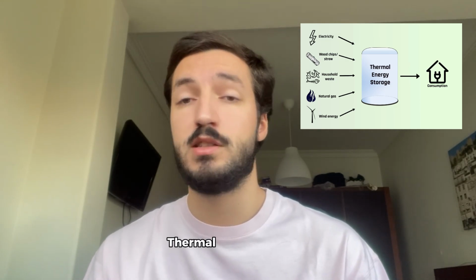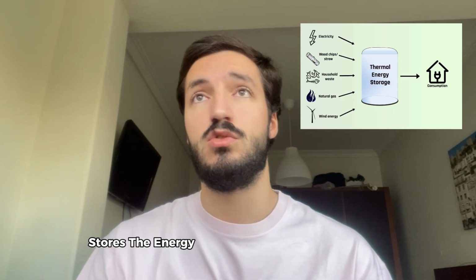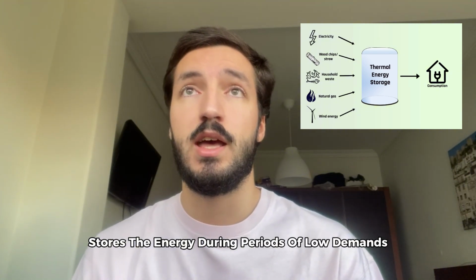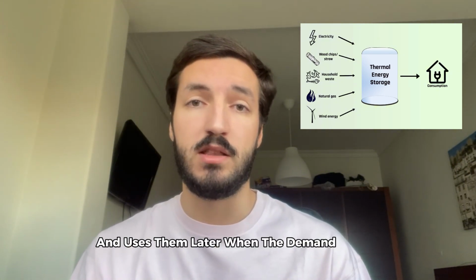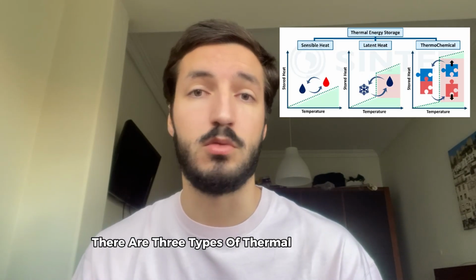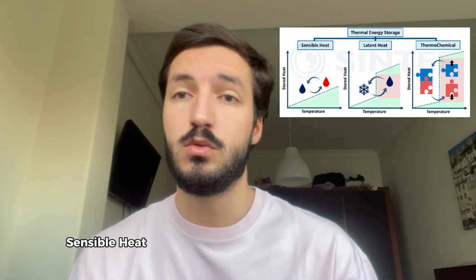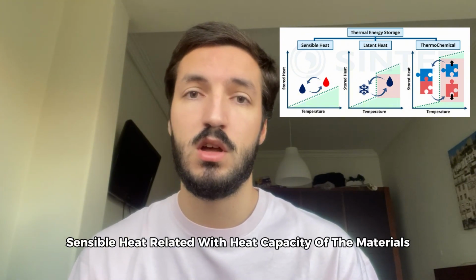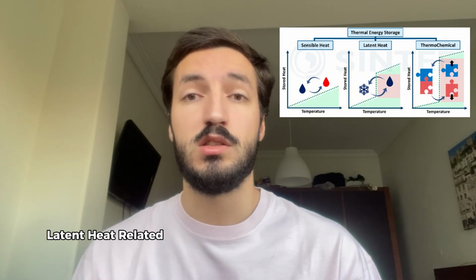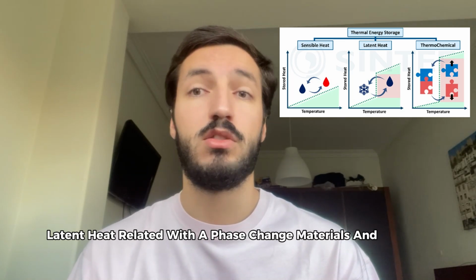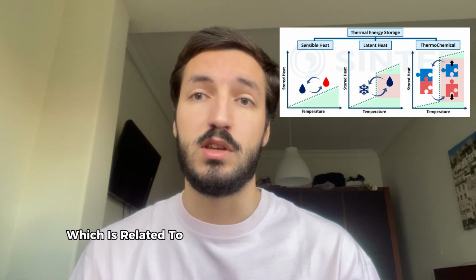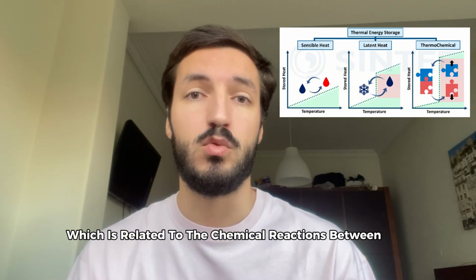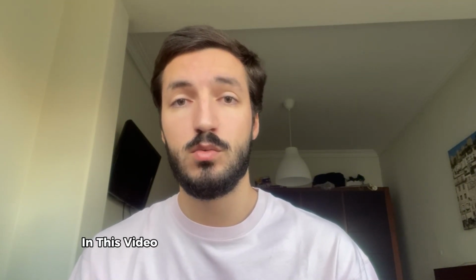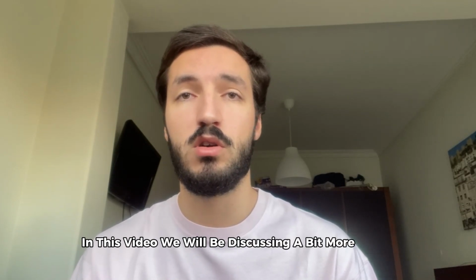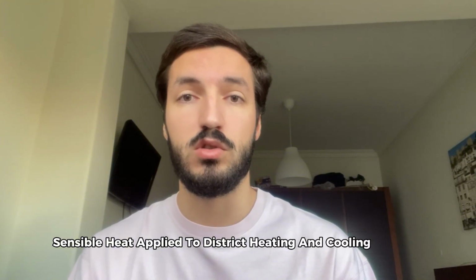Thermal energy storage stores the energy during periods of low demand and uses it later when the demand is high. There are three types of thermal energy storage: sensible heat, related with the heat capacity of the materials; latent heat, related with the phase change materials; and thermochemical, which is related to the chemical reactions between the materials. In this video, we will be discussing a bit more about sensible heat applied to district heating and cooling systems.